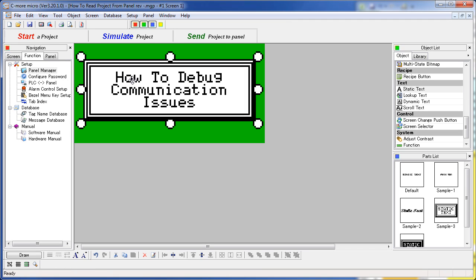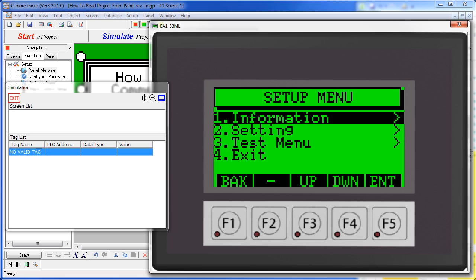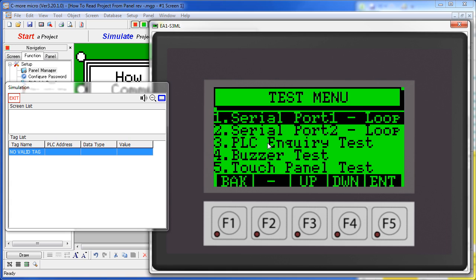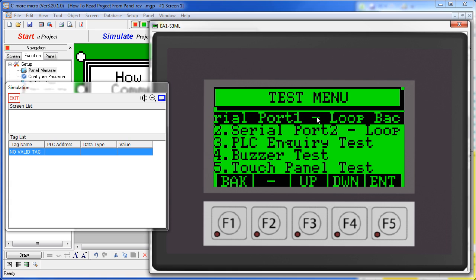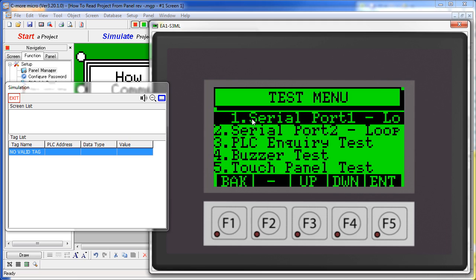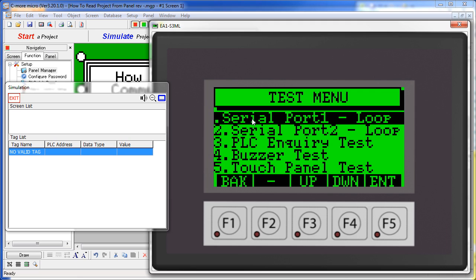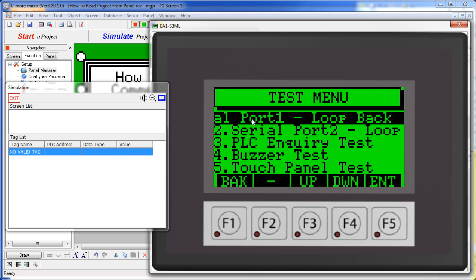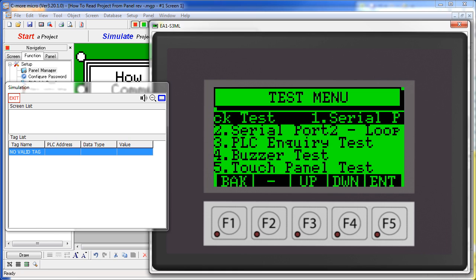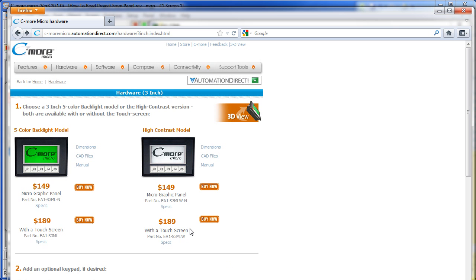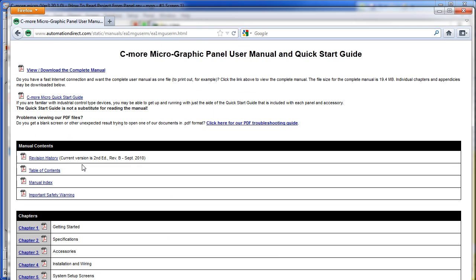Number 4: Verify that the COM port on the C-more Micro is good. To do that, just bring up the setup screen on the C-more Micro – I have a simulated version here – go to the test menu and there is a serial port loop back test. You will need a loop back cable or adapter which you can make yourself using the instructions in the hardware manual. If you go to the C-more Micro page, I am using this panel, so I will click on its manual. I am going to go down to chapter 5 in this manual which is the setup screens.